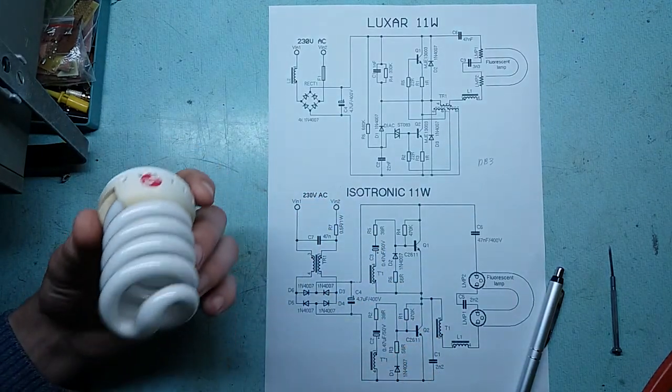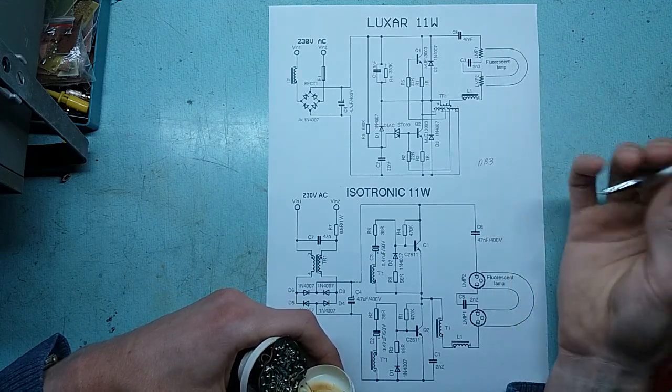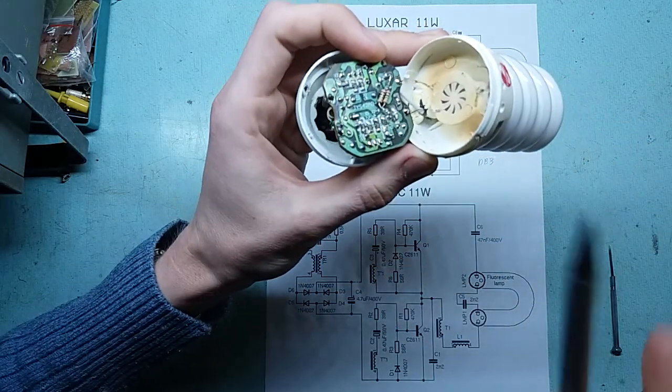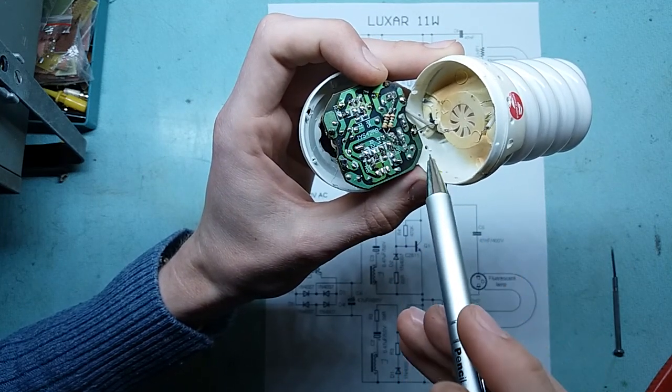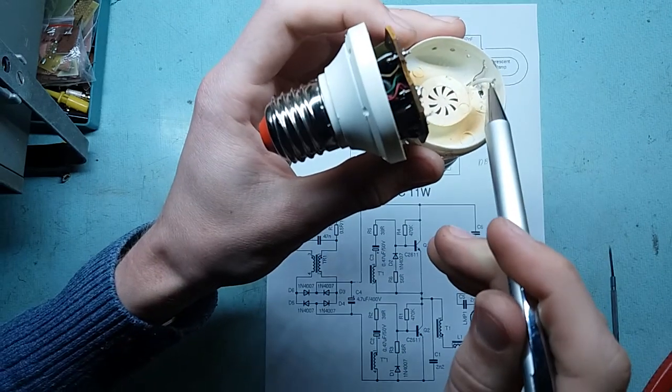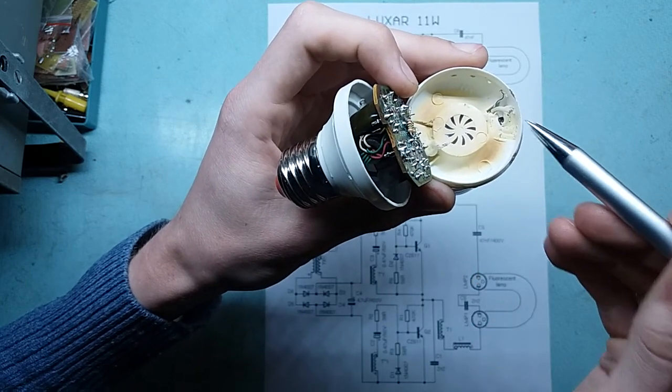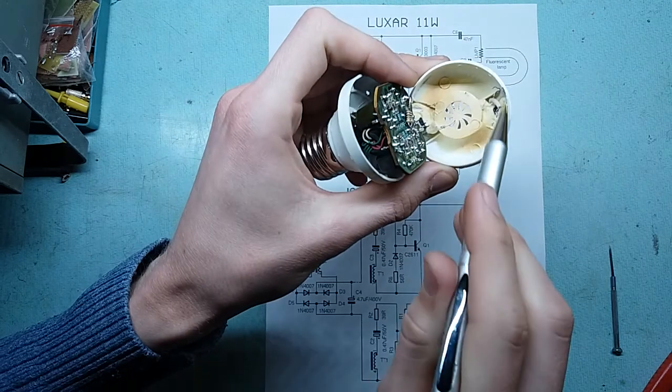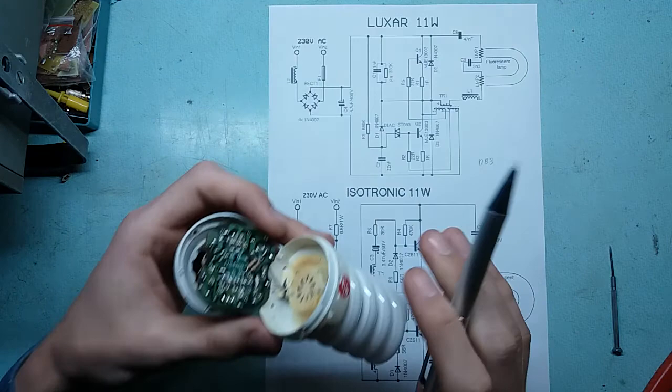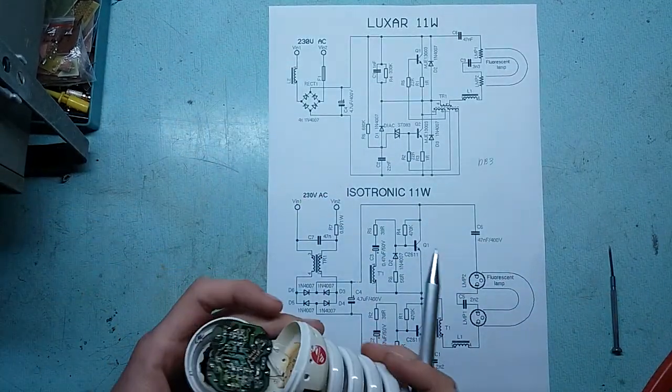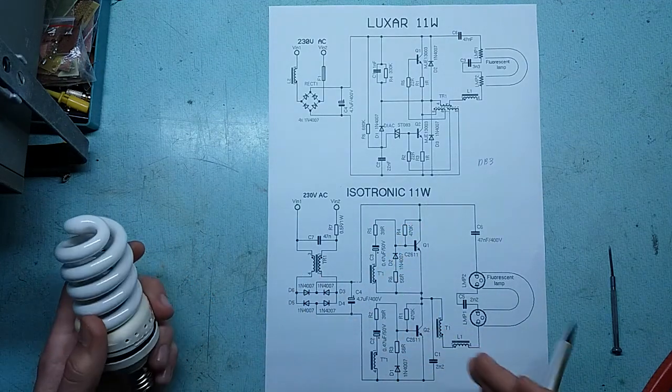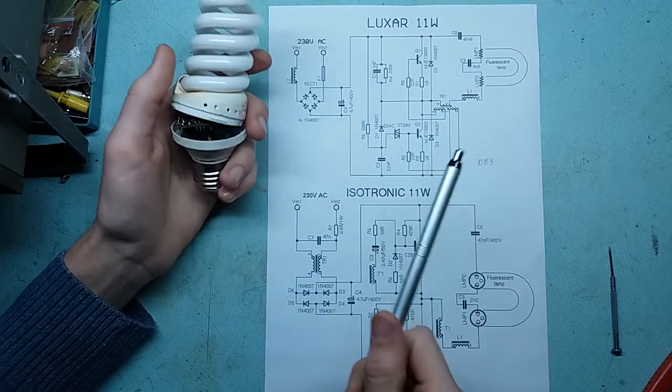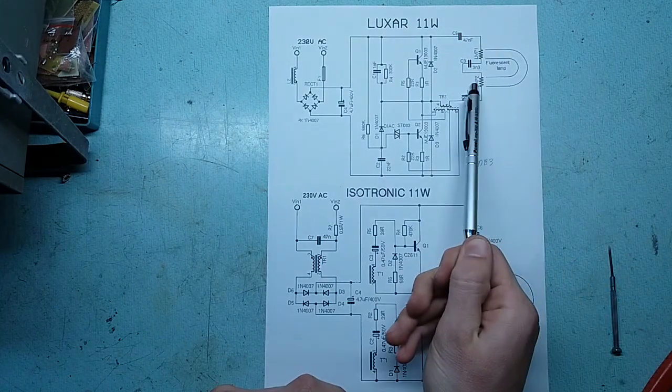Next, since the lamp is absolutely dead what you should really check straight away is to check the tube itself. The fluorescent tube has two filaments in it. You can see it has four wires, one wire there in insulation, another there and two here. Between each of these, between these two should be a continuity, about 10 ohm or so of resistance. Same applies to this pair. Between these two should be a continuity and between these two should be a continuity. If there is none, the tube is shot. Just toss it away. Now toss it into the recycling bin in a proper place. Okay, so let's say the tube is dead, then you can get the ballast and use it for something else or part it out. But let's say the tube is okay, both filaments are fine.